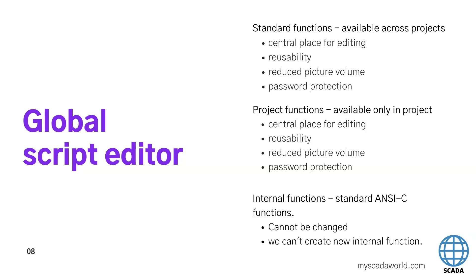Project functions are the same, but they are only available in one project — only the project where you created them. If you want to have them in all projects, you need to copy and paste to another project. Any other options are the same as in the standard functions. The last option is the internal functions. Here we have the standard WinCC library. The user cannot change these functions and we cannot create new internal functions — it's the standard WinCC library and we can use this inside our application.